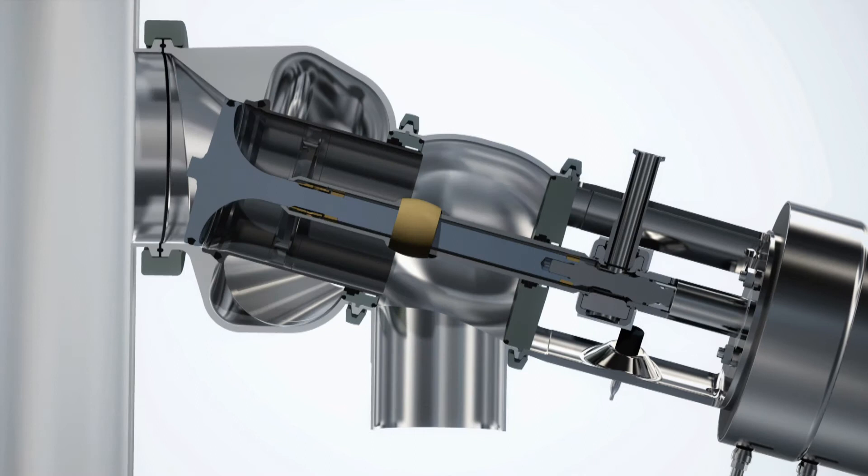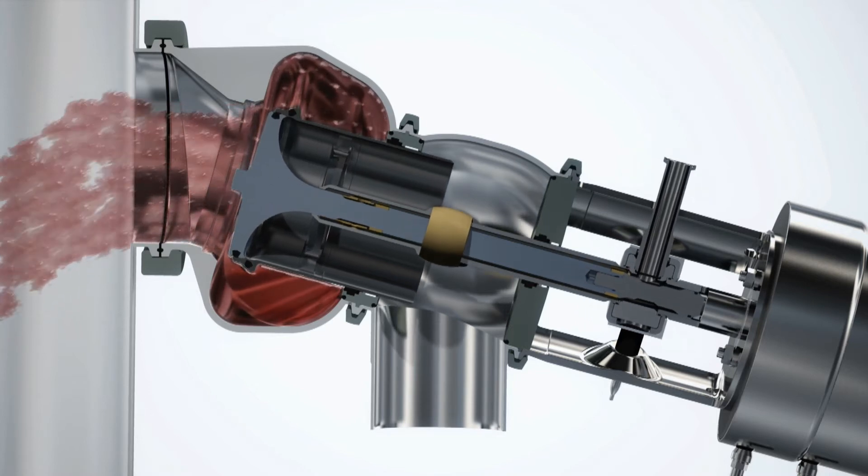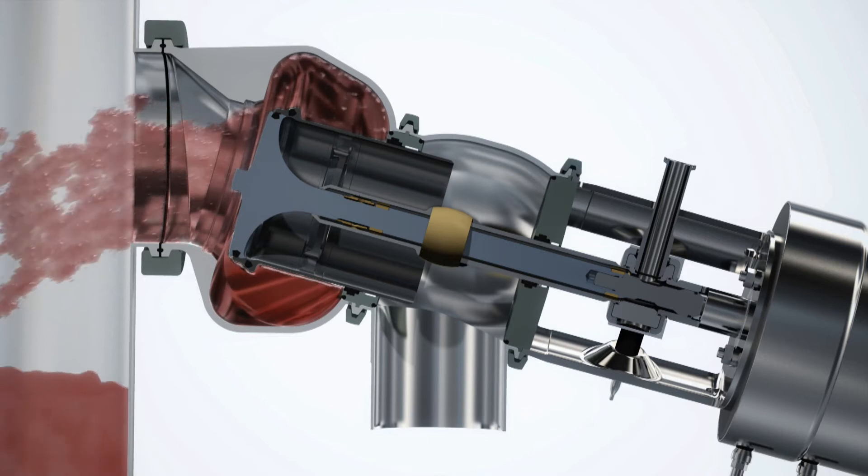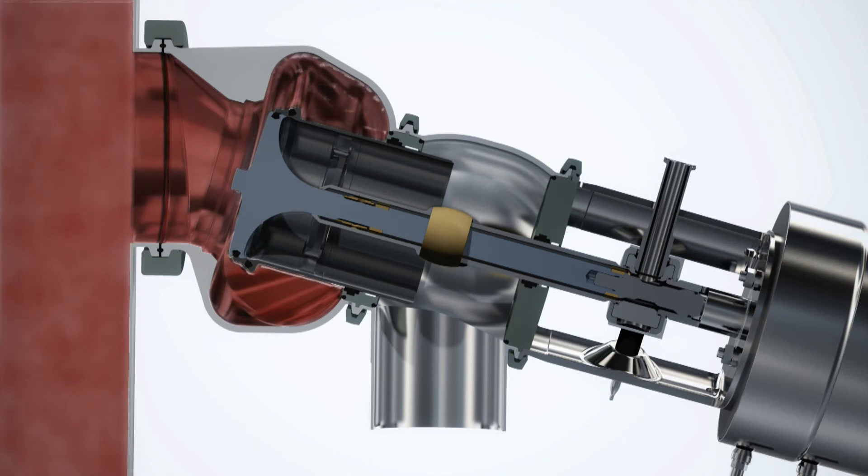When side-mounted, the unique mix-proof horizontal tank valve can serve different purposes. It can be used in tanks such as mixing tanks that require a separate inlet and outlet. When placed on the side of the tank, it helps reduce air entrainment because liquid is returned below liquid level. It can be used as a filling valve in places where it is advantageous to continuously fill an empty line separately, such as for fermented products. It can be used as a dosing valve.